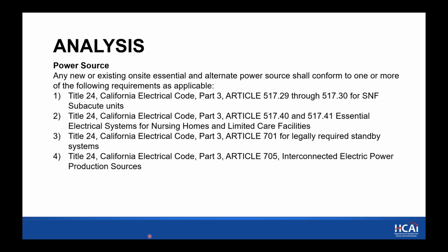As the bill is written, it's not specifically requiring that this equipment be on the emergency branch. So depending on how the solution or proposed upgrades are presented, you could either be following the California Electric Code Article 517, 517.29 through 30 for subacute SNFs, 517.40 to 41 for standard SNFs, or you could come up with a design that's independent of the essential system, in which case you would either be required to follow Article 701 for legally required standby, or Article 705 for interconnected electrical power production sources. I'll go into a little bit more detail on those later in this presentation.